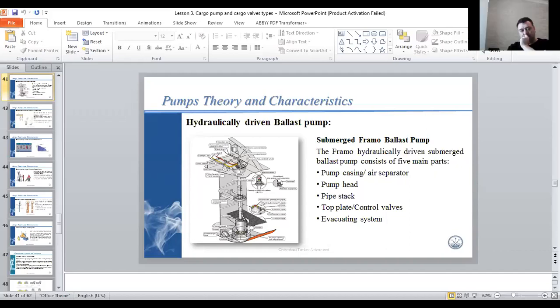Correct operation of pumps and valves avoids pressure shocks in the cargo pipeline system during loading, or severe damage to pipelines, hoses, loading arms, and cargo pumps. To avoid pressure shocks, start the loading slowly and don't open or close the cargo valves in the system too quickly, especially when long pipelines and high flow rates are involved.